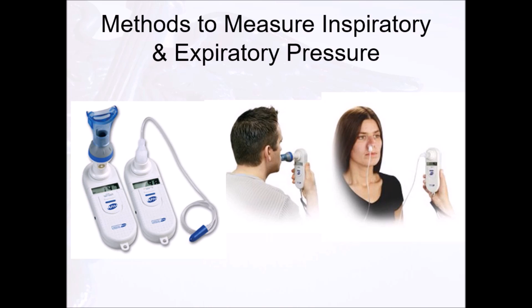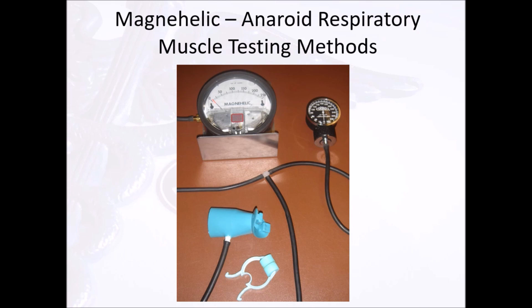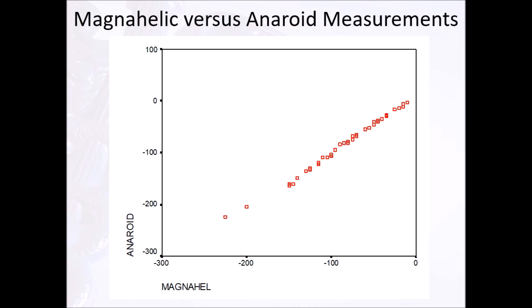We can also use a sphygmomanometer, a blood pressure taking device, which in fact my colleagues and I have done. We've tested and we find that although the blood pressure cuff is measuring blood pressure, a positive pressure, when we inflate this, we have a positive pressure reading. The valve actually moves backwards if we inspire through it, and it provides us with a pressure in centimeters of water, and that particular pressure is almost identical to that which we've obtained with Magnehelic gauges and pressure transducers, such that we see an almost perfect correlation in this particular slide.